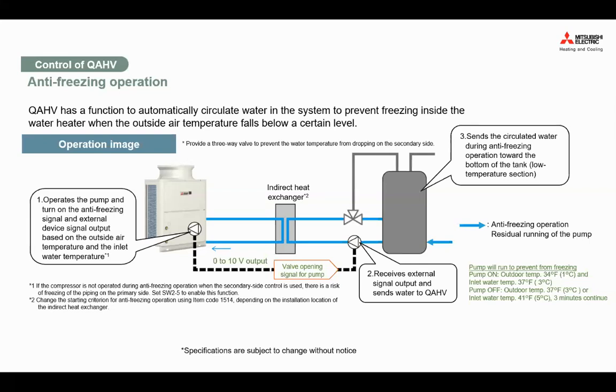So basically, the pump will run to prevent freezing when the outdoor temperature is 1 degree C or less and the inlet water temperature is 3 degrees C or less, right? However, the pump will be off when your outdoor temperature is 3 degrees C or your inlet water temperature is 5 degrees C for more than 3 minutes, right? That is just to recirculate, to make sure the water does not freeze inside the heat exchanger and does not freeze inside the unit itself.